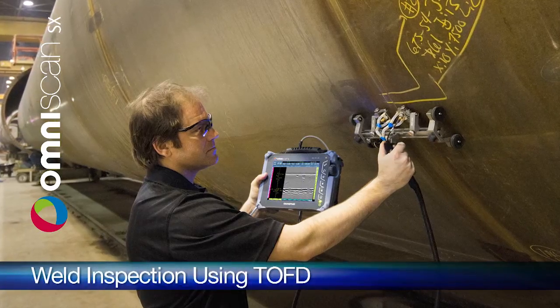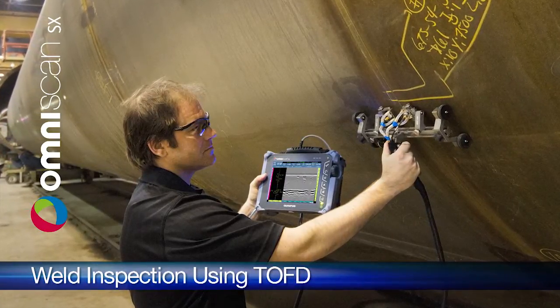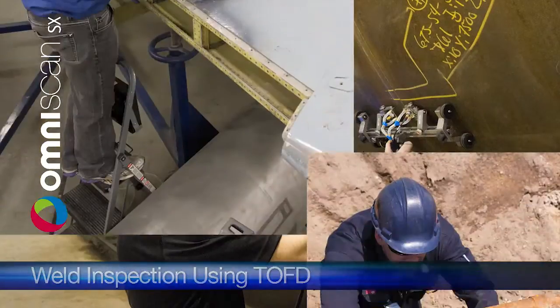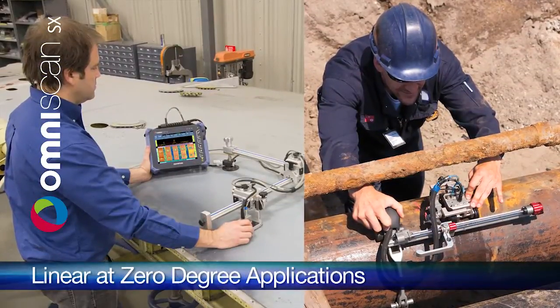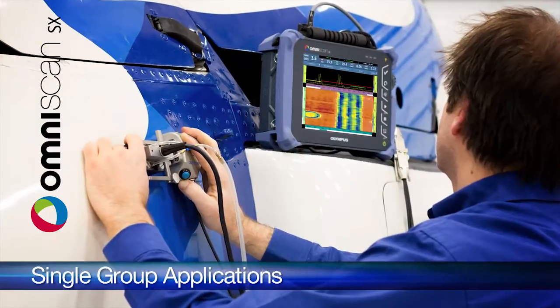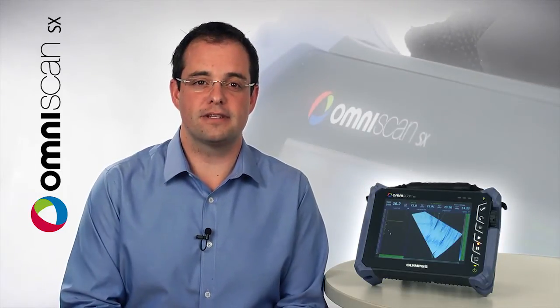The common applications for the OmniScan SX are weld inspections using TOFD technique or phased array. The SX can also do linear at zero degree applications such as corrosion mapping and composite inspection. Other applications requiring a single group can be accomplished using the OmniScan SX. With the introduction of the OmniScan SX, Olympus NDT continues to expand the coverage of the OmniScan family, making phased array technology more accessible and affordable.